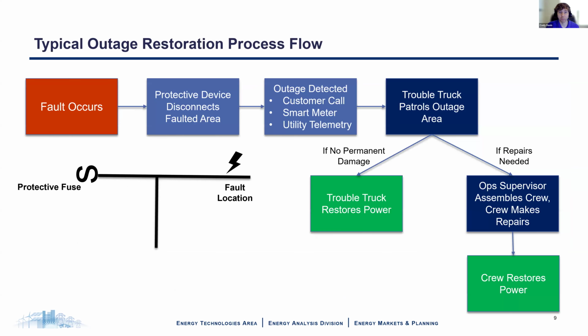So now we're going to look at what that process flow actually looks like for an outage. So we have our fault that occurs. I've got my fault lightning bolt over here. My protective device disconnects the entire faulted area downstream. So in this case, it's a fuse. The outage gets detected by one of a couple of different means. Either customers can call in and say, hey, I'm out of power.